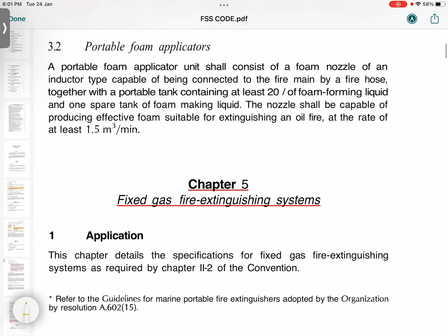You see, this is portable, right? So a portable foam applicator shall be used with the foam nozzle. A portable tank containing 20 liter of foam forming liquid and a spare tank of foam making liquid. The nozzle is capable of producing effective foam suitable for extinguishing oil fire at a rate of at least 1.5 meter cube per minute. Okay, don't worry.